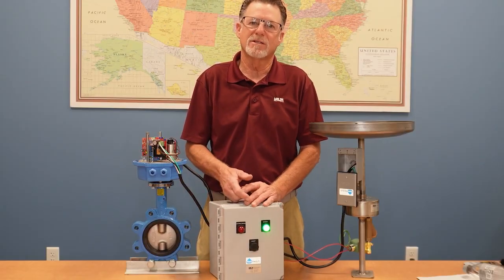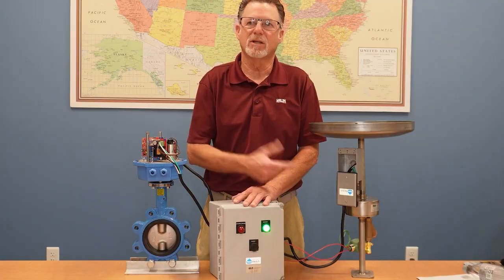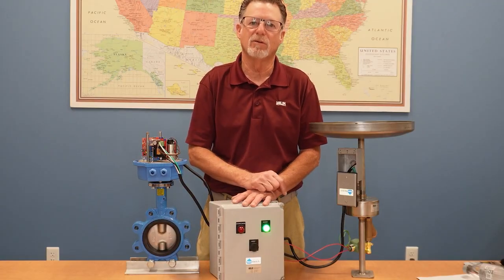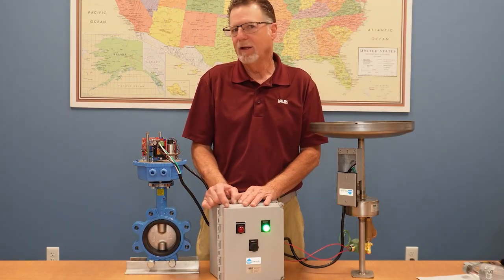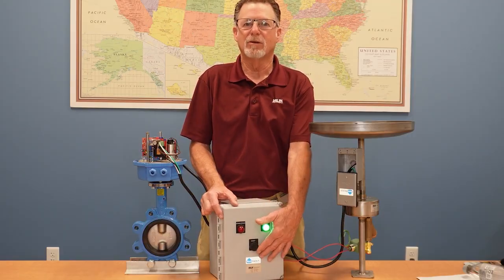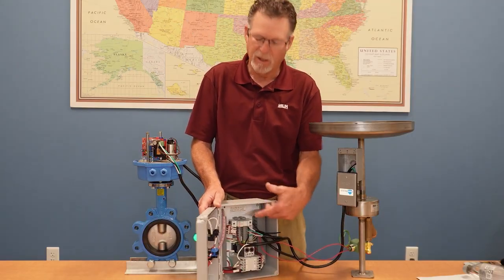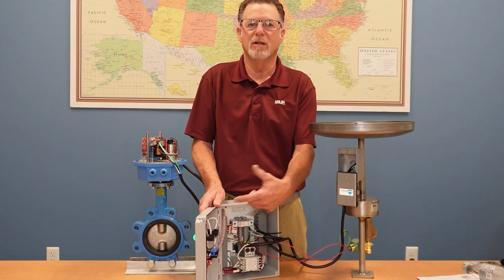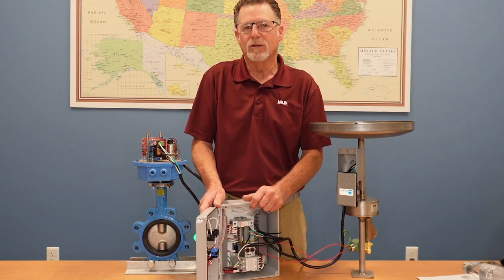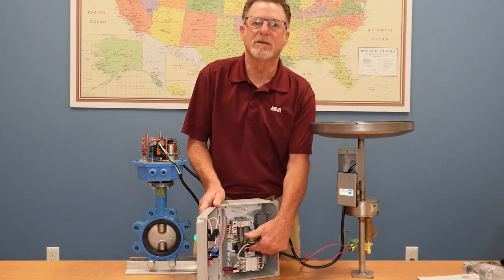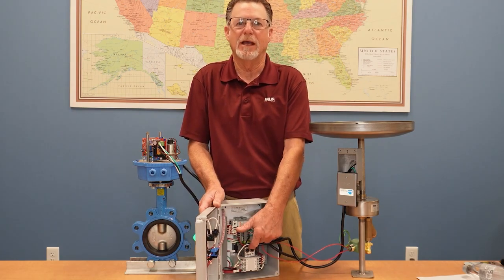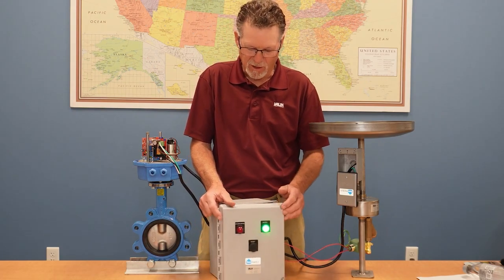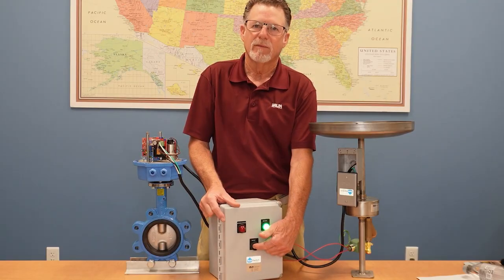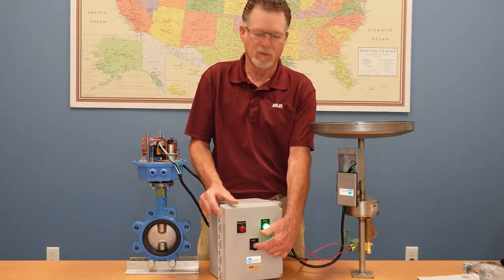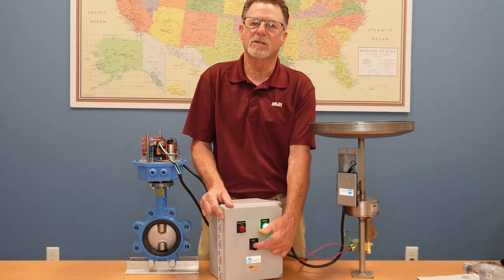This allows it so that the system doesn't get just left for a month or two in the divert condition. LA County doesn't like it. They only want the manual reset. So the only difference between this automated version and the manual is this timer is lacking. It's not in the manual. The only way you open the solenoid is you can hear it actuate. Okay, you hold it until the water stops coming out of it, till it's completely drained.